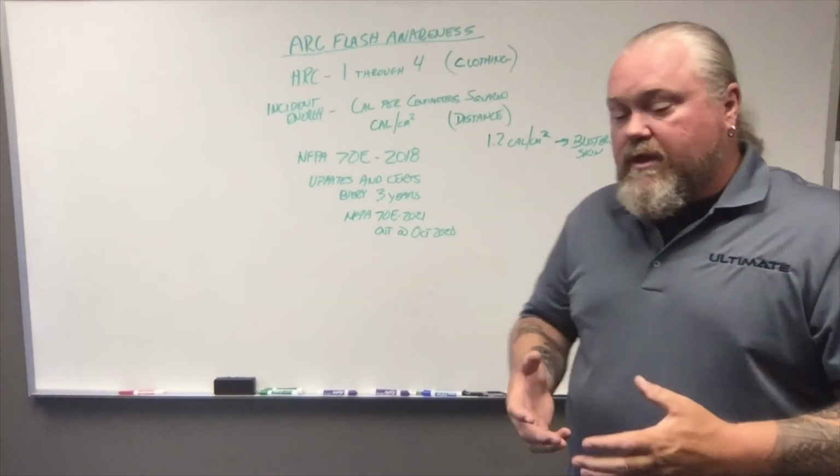We want to ensure that before you get started in any activity, that you review the NFPA 70E according to not just the arc flash protection that you need to do, but understand that just because a label says that you're okay to be around it at an HRC 1, if you start diving into that equipment, to do meter testing, to do alterations, pulling lines, things of that nature, the game changes. And then you need to go into those tables to find out, one, what your activity is, two, what the equipment potential is, and then three, that would give you your HRC protection stance when you do that.